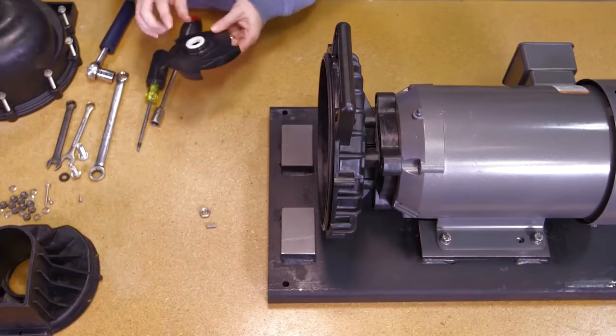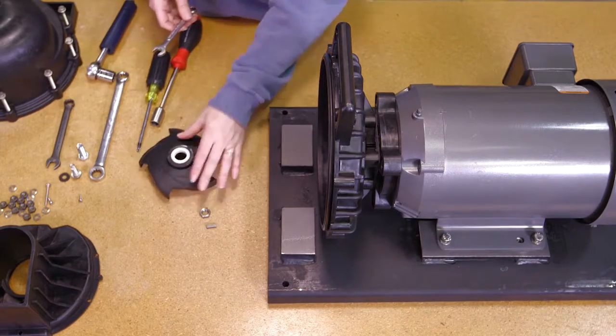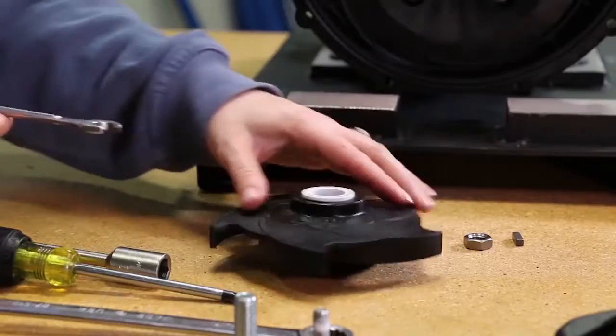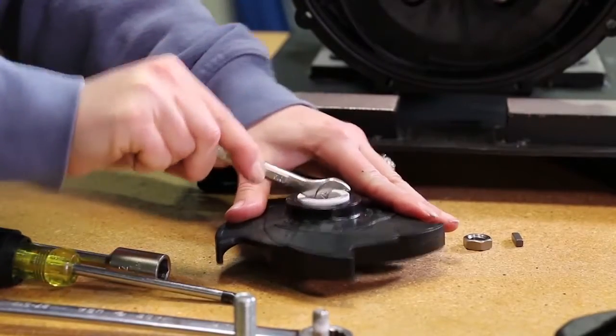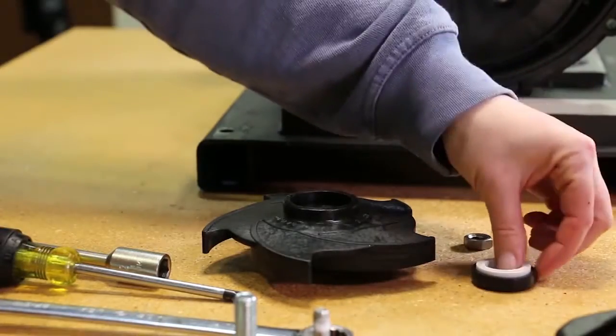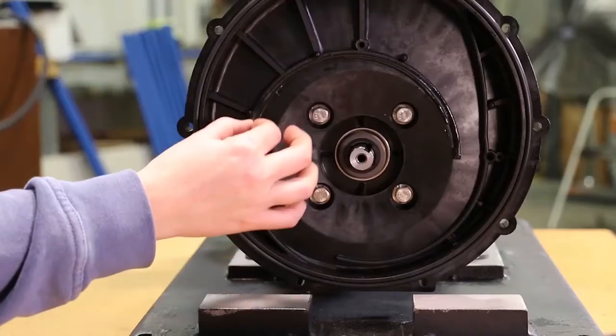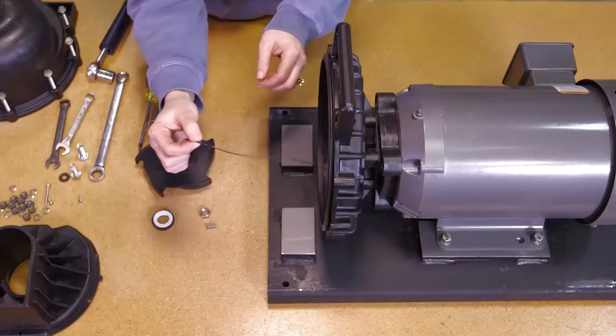If the pump impeller is going to be reused, the ceramic seal half should be removed from the impeller at this time. Using a screwdriver or wrench, gently wedge the seal out of the impeller. Please use caution when removing ceramic seal to prevent any damage. Remove the O-ring segment at this time.